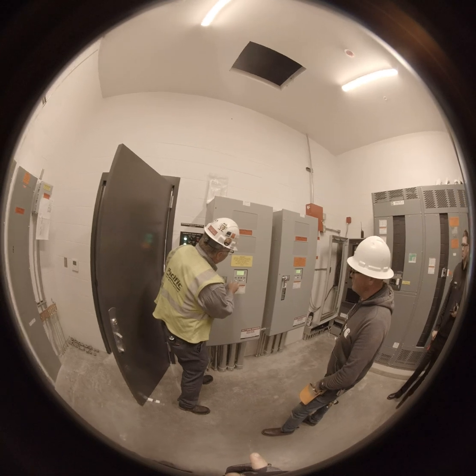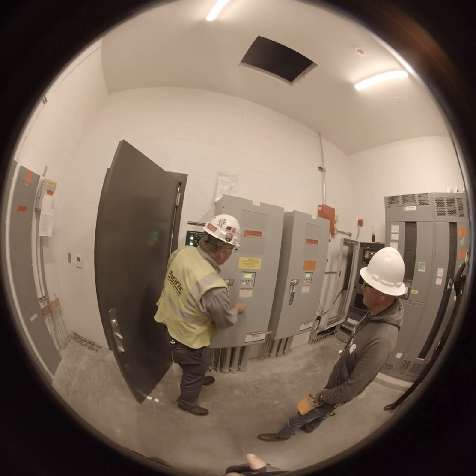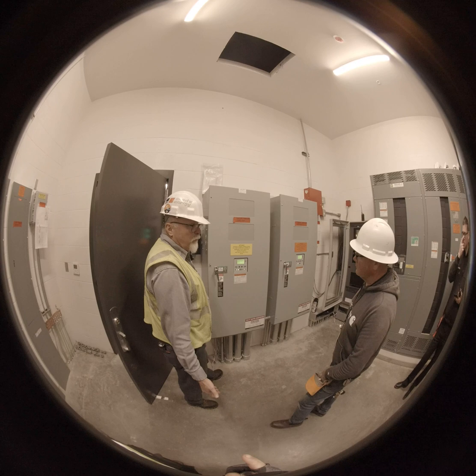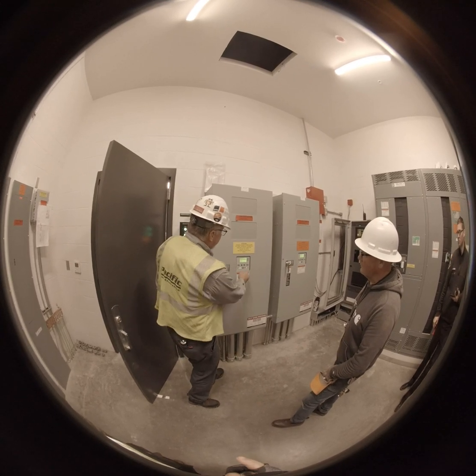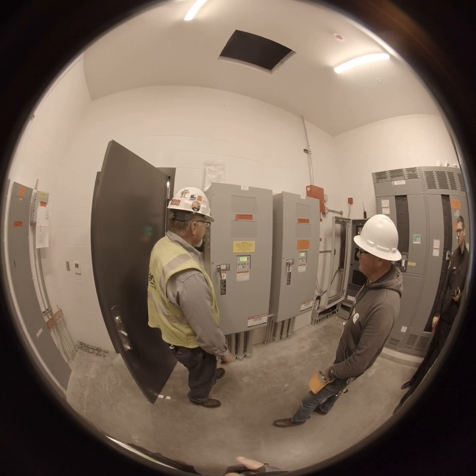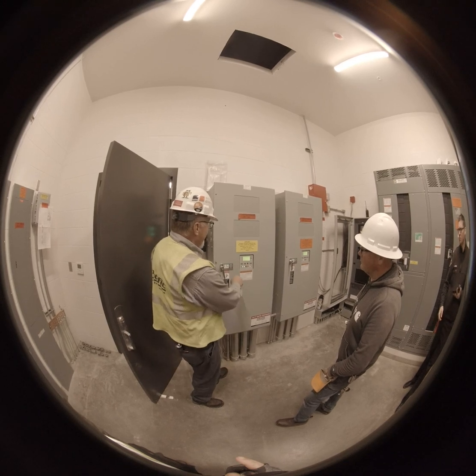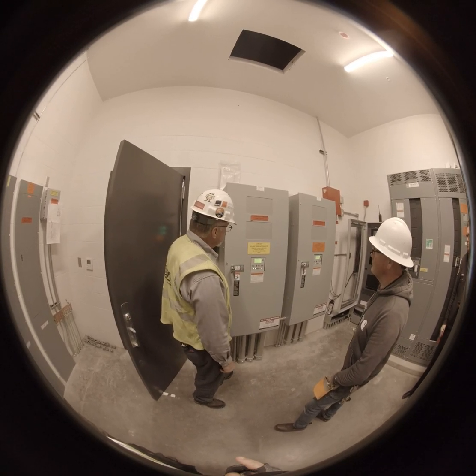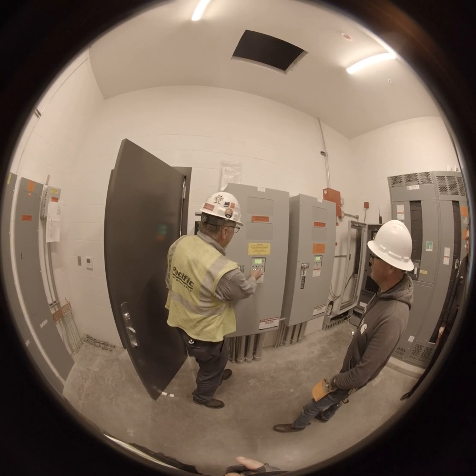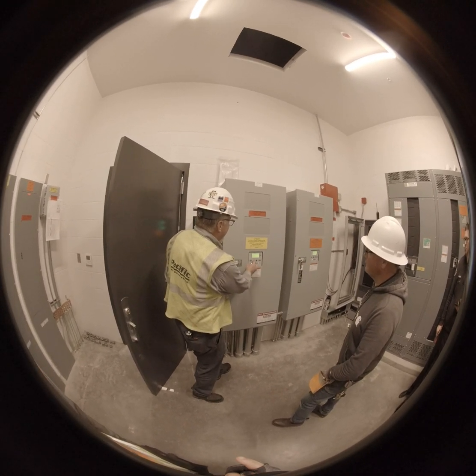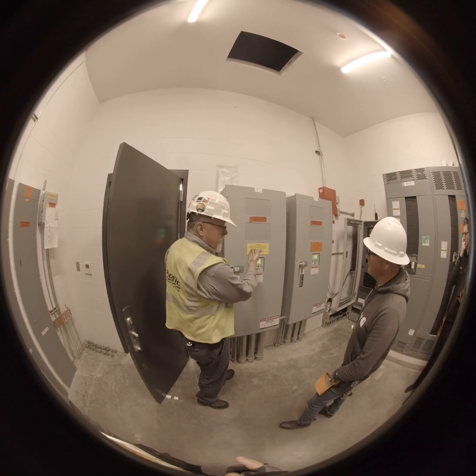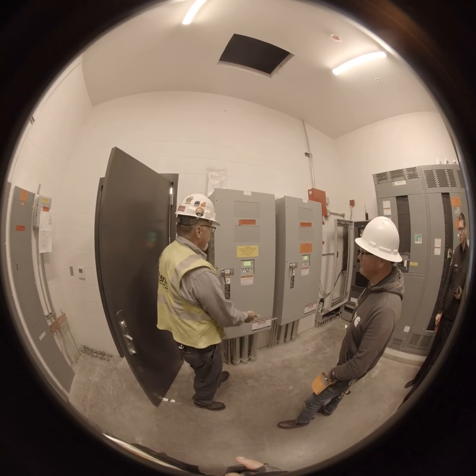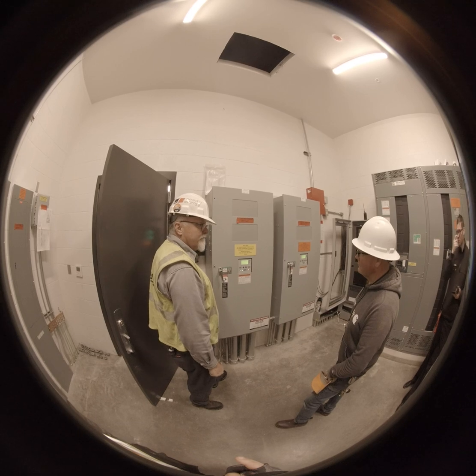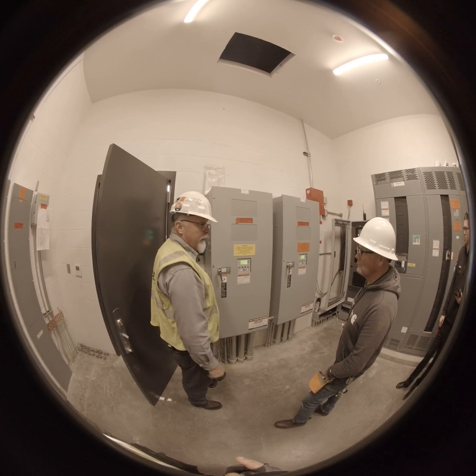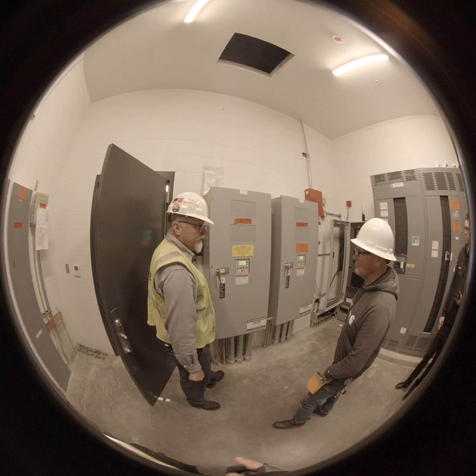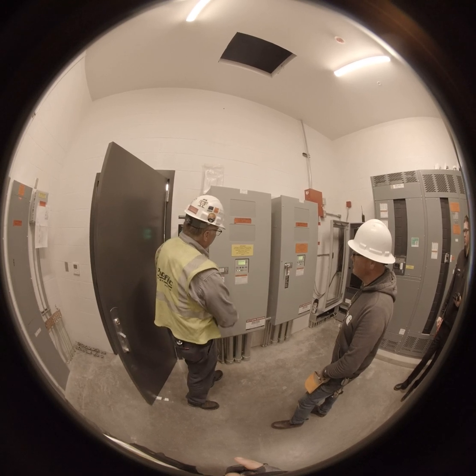So we're going to go this way. You can read events like you did on the generator set. It tells you what happened, when it happened, the whole nine yards. Event 2, oh, let's go the other way. Go up. There's event 2, and there are like 160 events you can go through, so you can track what's been going on. That's what I'll do if they have a transfer switch issue. I'll just go back and start reading the events on it. Escape out.